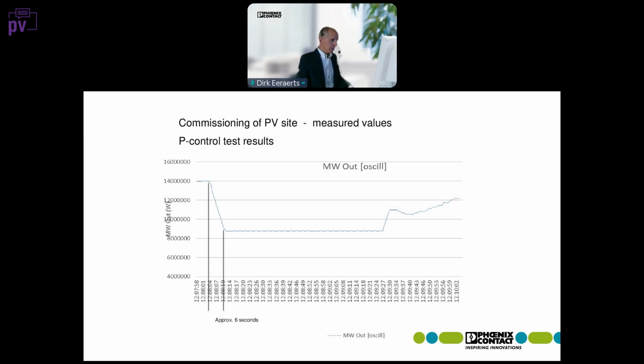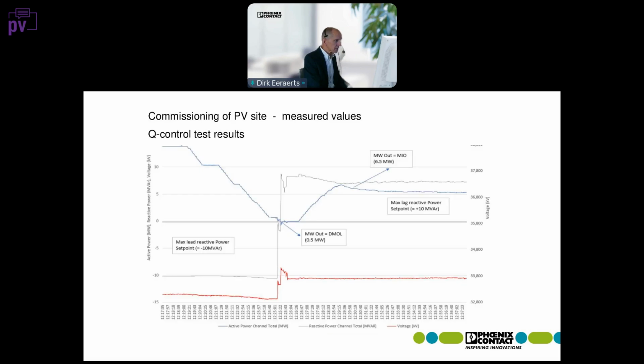During this commissioning, a number of tests have to be gone through, and they have to be documented in detail with detailed power analyzers or even with oscilloscopes. You have to apply ramp rates, you have to maintain certain values, etc. So this is just active power. This one is a bit more interesting.